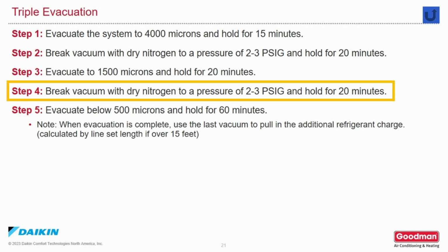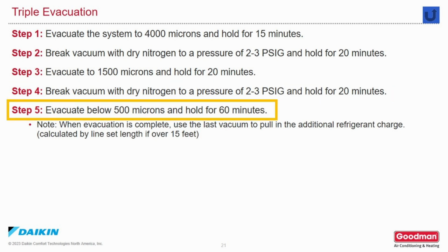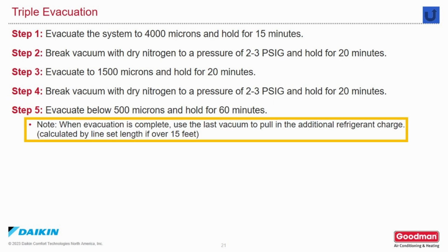Break that vacuum with nitrogen, pressurizing to 1.5 to 3 psi and holding for 20 minutes. Your third and final evacuation should be at least 500 microns or below for 60 minutes. Make sure you do a 60-minute rise test to ensure that that line set is sealed and dry. Once the evacuation is complete, you can use that final vacuum to pull in the additional refrigerant charge if it's needed. The system is charged for 15 feet of line. Consult your installation manual for calculation of additional charge for line sets over 15 feet.